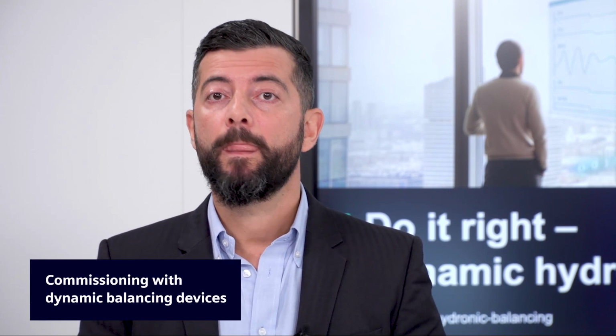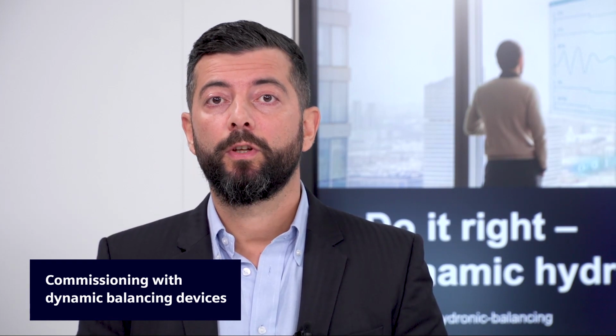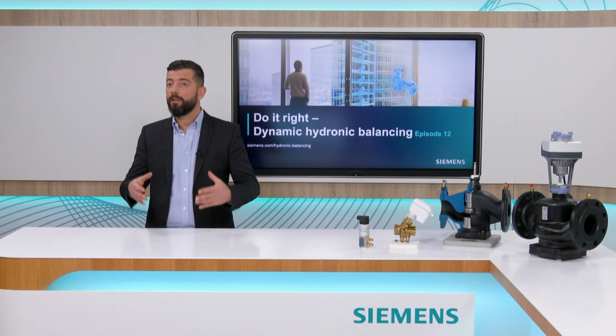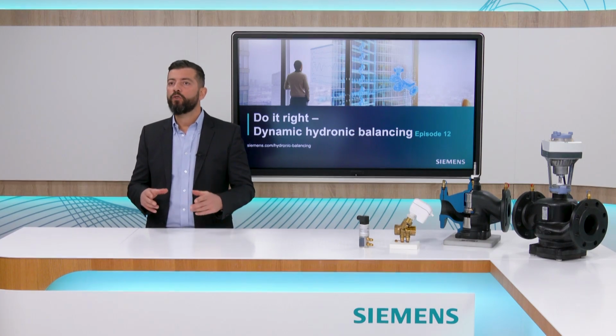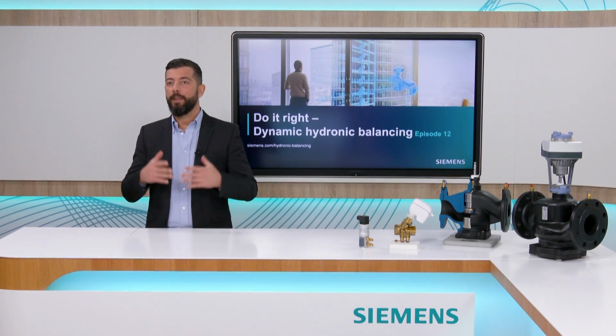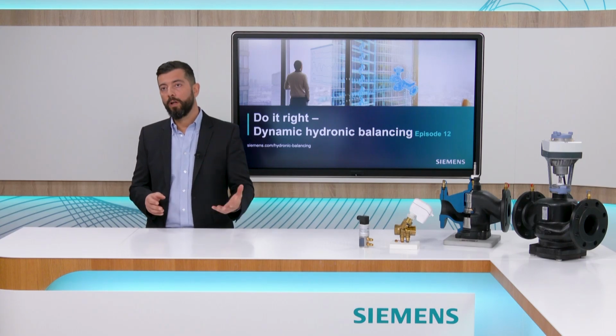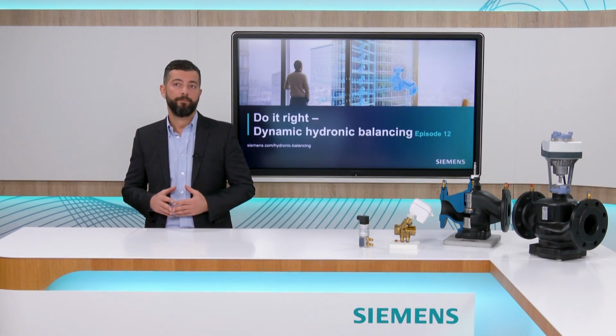Today, we will continue to explore how to improve the performance of a hydronic distribution system by maintaining a particular focus on the interaction between pumps and valves, and especially what needs to be done during the commissioning phase. The commissioning process mainly comprises the proper setup of the system pumps and the proper regulation or balancing of flow rates before the heating or cooling system can be finally put into operation and handed over to the client, the owner of the building, or its representative.